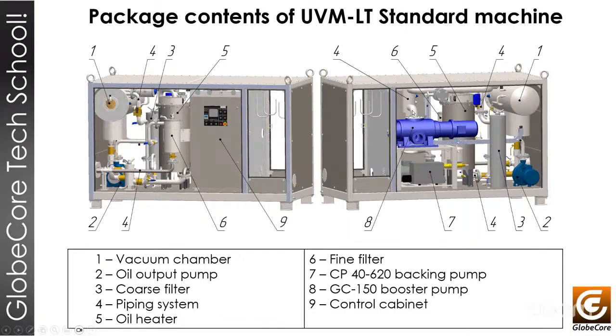Okay, this is the piping system, and it has the oil trap because we must be very careful not to mix the transformer oil with the vacuum pump oil. These traps help us avoid alarm conditions, because when you have mixing of oils you can have problems. The machine has a double system to prevent these conditions, and the oil traps are one of the systems to prevent this possible problem in our machines.